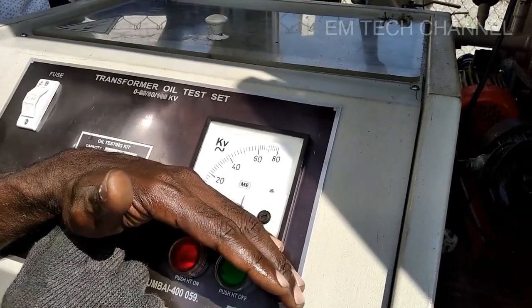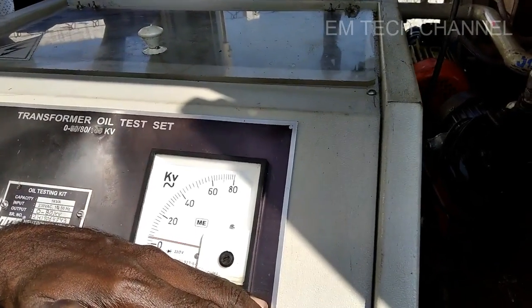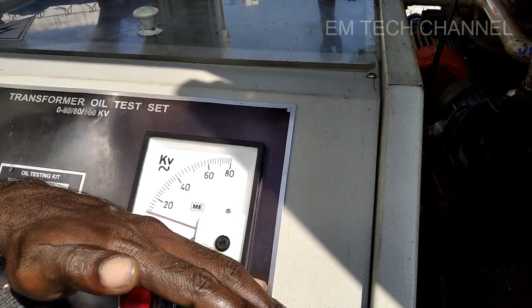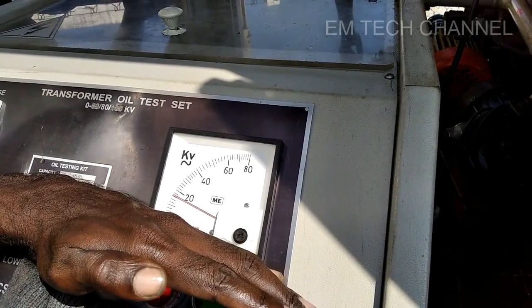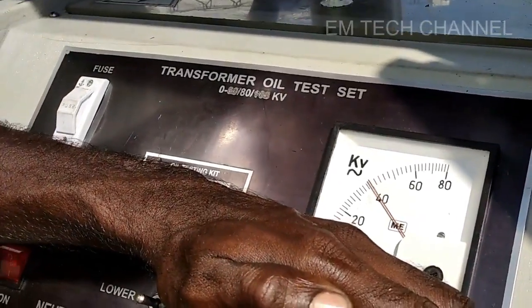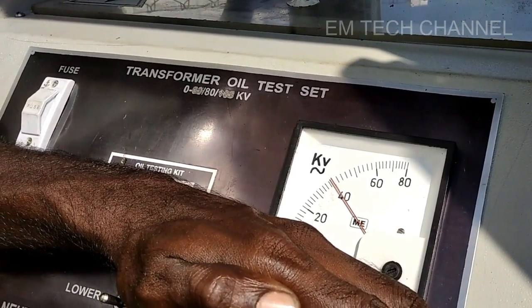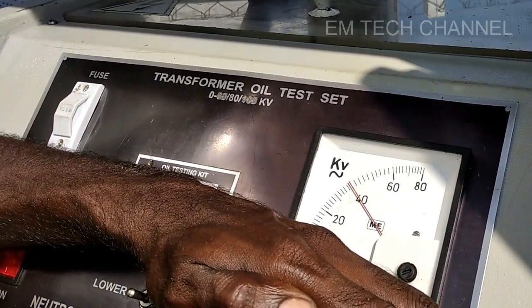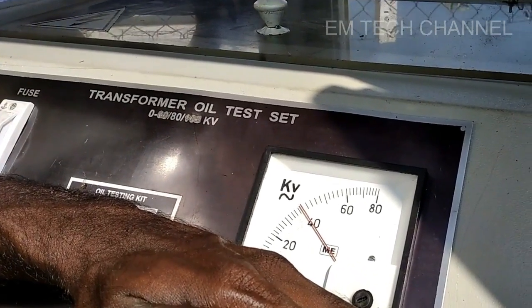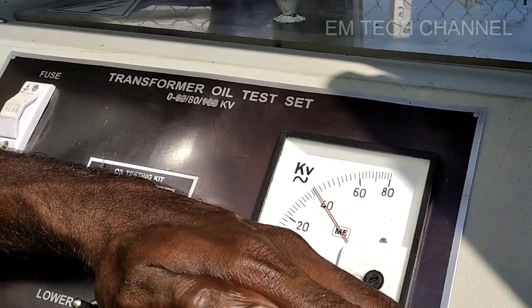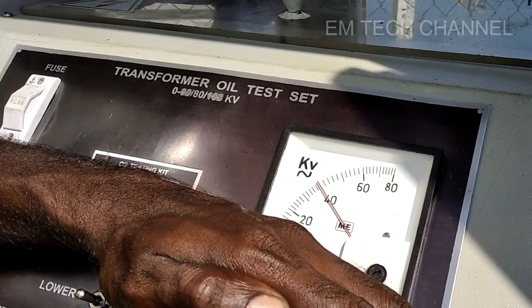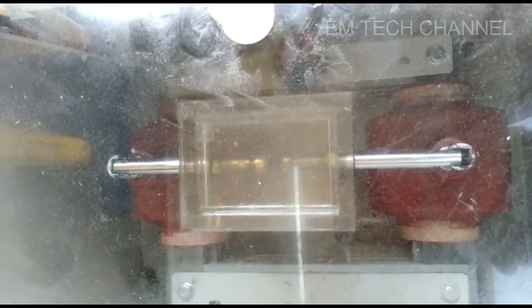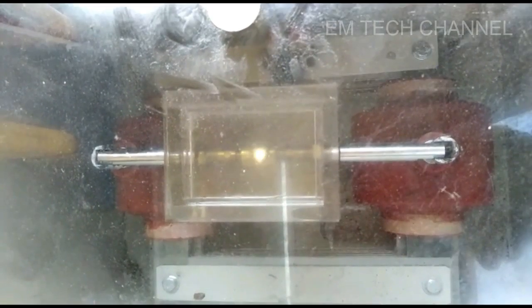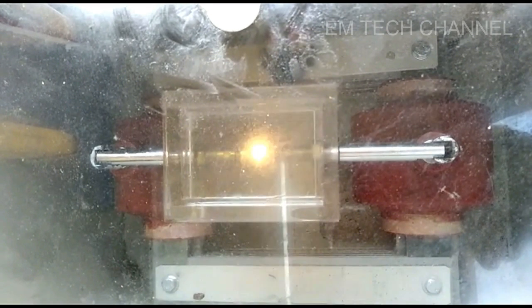Now we are increasing the voltage gradually by pressing the HT on button, shifting the toggle switch to right, and you can see the voltage is increasing, and we increase up to 40 kV and will wait for 1 minute, and now as 40 kV is successfully withstood, we are increasing further and you can see the breakdown will occur now. You can see the test cell with two electrodes of 2.5 mm gap between them, and you can see now the breakdown occurred and is evidenced by the way of spark, and you can see it in slow motion. And this is how breakdown test is being carried out.